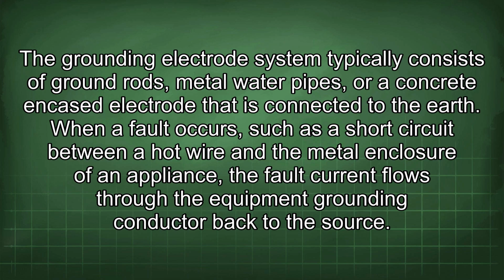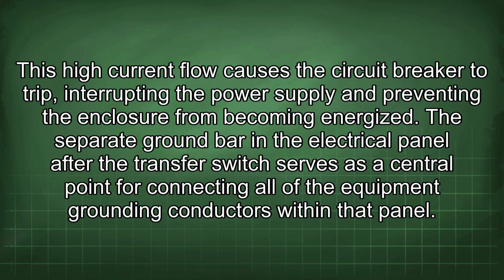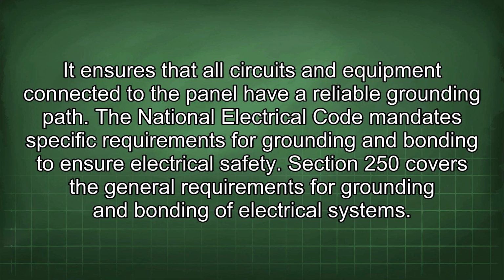When a fault occurs, such as a short circuit between a hot wire and the metal enclosure of an appliance, the fault current flows through the equipment grounding conductor back to the source. This high current flow causes the circuit breaker to trip, interrupting the power supply and preventing the enclosure from becoming energized. The separate ground bar in the electrical panel after the transfer switch serves as a central point for connecting all of the equipment grounding conductors within that panel. It ensures that all circuits and equipment connected to the panel have a reliable grounding path.